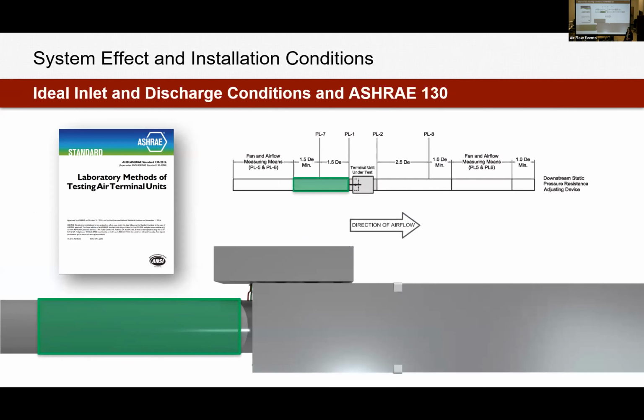What is the actual way to do this? ASHRAE 130 is the method of test for terminal units. So all of the catalog data is tested in this very nice configuration. ASHRAE 130 tells us that we have to have 3 equivalent duct diameters of straight hard duct on the inlet valve of the terminal. And then on the discharge, we have to have 2.5 equivalent duct diameters of straight hard duct on the discharge. Now, again, you're usually probably not going to see this. Engineers don't often have that much space. Contractors don't have that much space and might not install it if the drawings are laid out that way. So this is how all of the catalog performance is measured and tested, but on site, again, you might not actually get here.